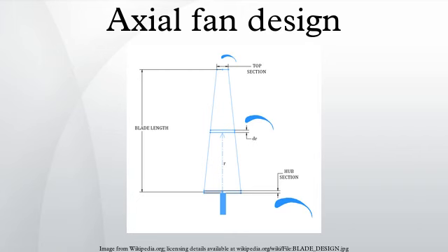VFDs are not practical for some axial fans. Many axial fan failures have happened after controlled blade axial fans were locked in a fixed position and variable frequency drives were installed. Axial fans with severe instability regions should not be operated at blade angles, rotational speeds, mass flow rates, and pressures that expose the fan to stall conditions.